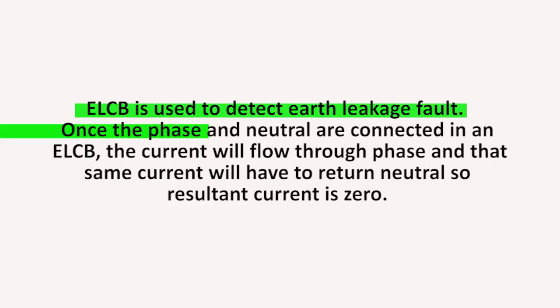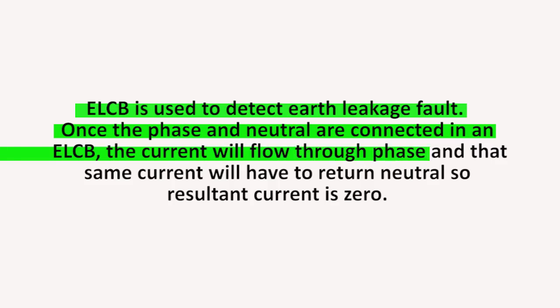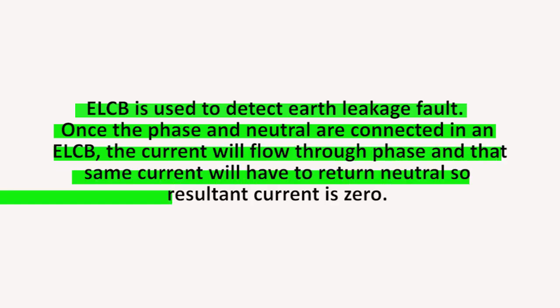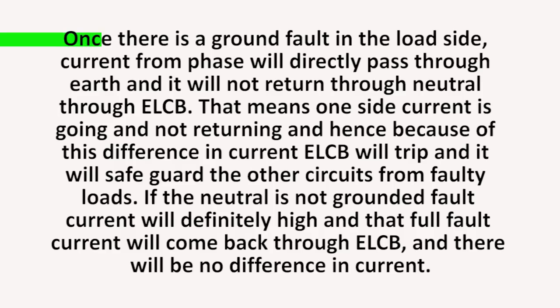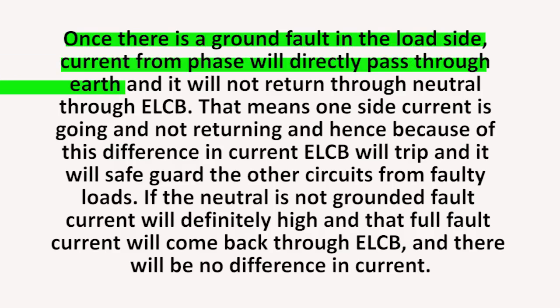Once the phase and neutral are connected in an ELCB, the current will flow through phase and that same current will have to return through neutral. So, the resultant current is zero. Once there is a ground fault in the load side, current from phase will directly pass through earth and it will not return through neutral through ELCB.